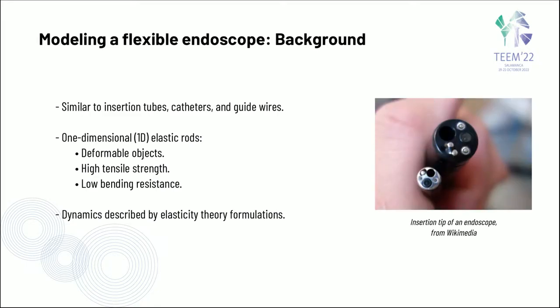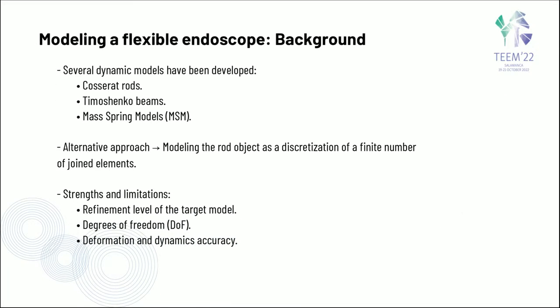The flexible endoscope shares features with slender objects like insertion tubes or catheters, commonly known as 1D-elastic rods — objects with high tensile strength and low bending resistance. To describe the dynamics of these objects, a common approach is to use elasticity theory formulations. From this approach, several dynamic models have been developed, like Cosserat rods or Timoshenko beams. An alternative approach is the discretization of the rods as a finite number of unit elements. Both approaches have strengths and limitations regarding degrees of freedom and dynamic accuracy of the resultant model.